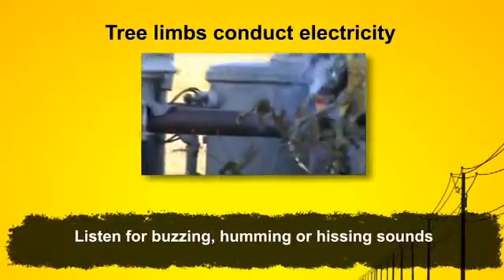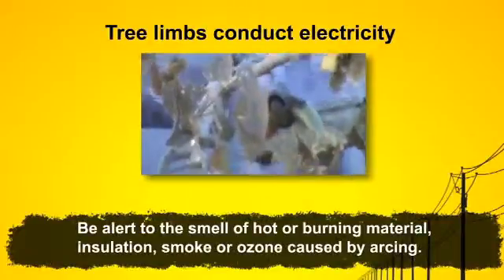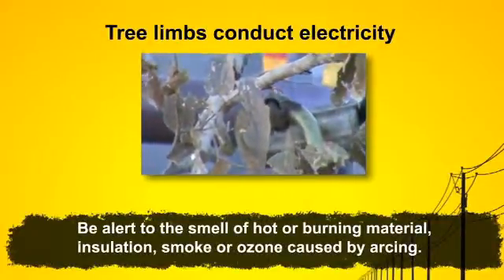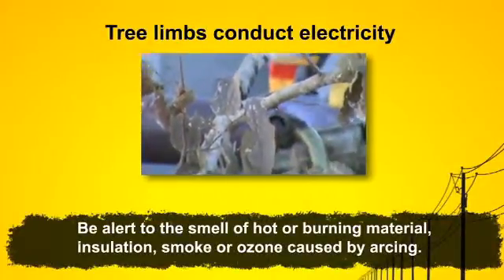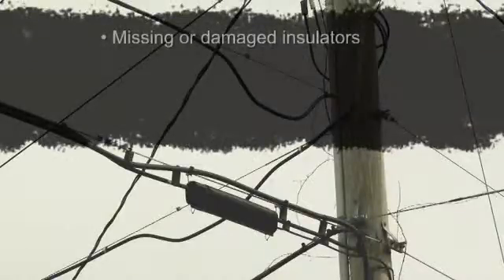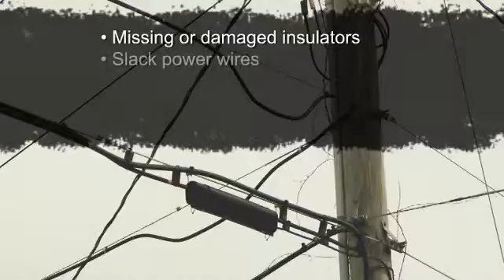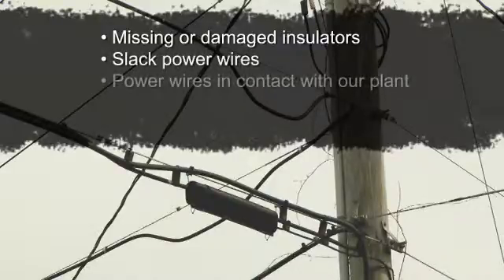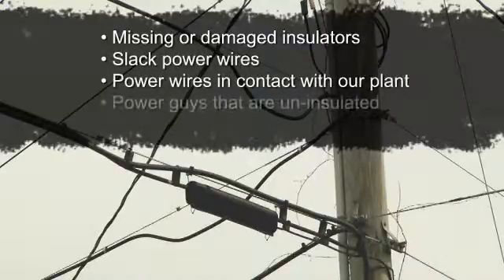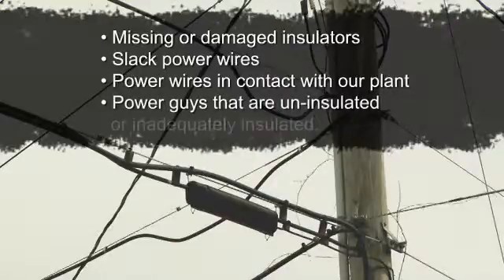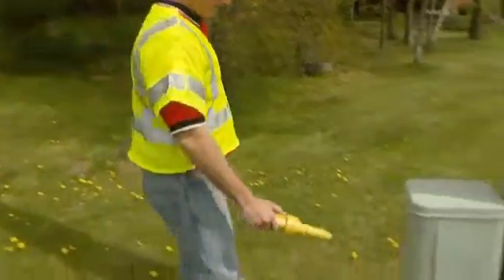Listen for buzzing, humming, or hissing sounds. Be alert to the smell of hot or burning material, insulation, smoke, or ozone caused by arcing. On power company equipment, look for missing or damaged insulators, slack power wires that don't seem to be attached correctly, power wires in contact with our plant, and power guys that run through our workspace and are uninsulated or inadequately insulated. Don't touch anything that might be an electrical hazard.